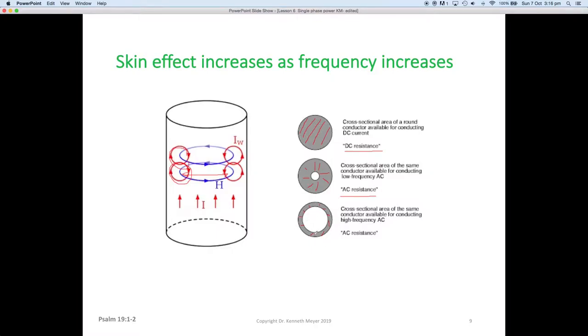So if you ever have an opportunity to go into big power stations or high voltage installations, you'll quite often see the conductors they're using, you think they're pieces of pipe. Well, they are pieces of pipe, quite often a piece of aluminum pipe. For high voltage they look like this. So why build a substation switching yard with all these conductors and have them solid when most of the current is going to flow on the outside anyway? So you'll find in a lot of high voltage substations, you'll see a lot of the conductors are actually hollow because they know there's this skin effect. Why bother having this area in the middle here if the power or the electricity of the current is not going to flow?